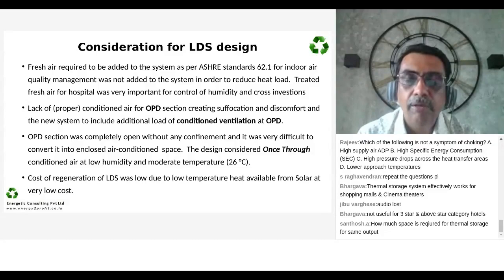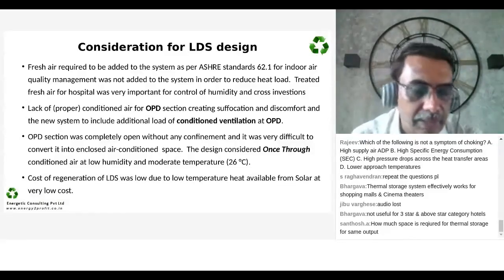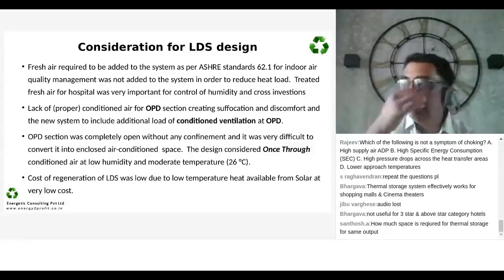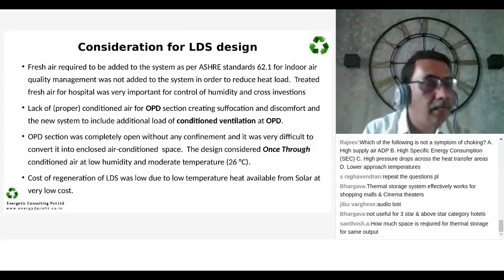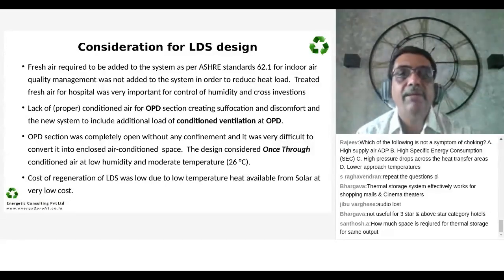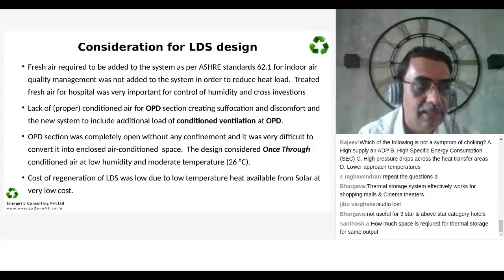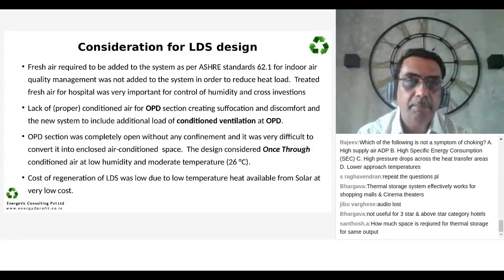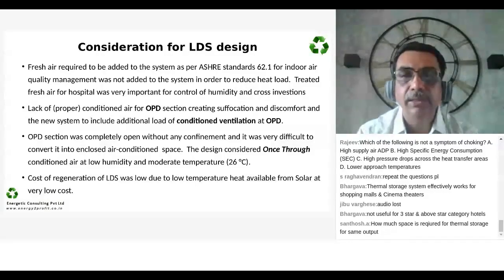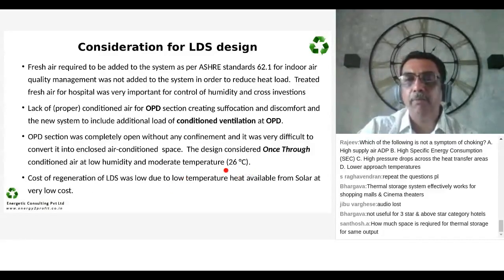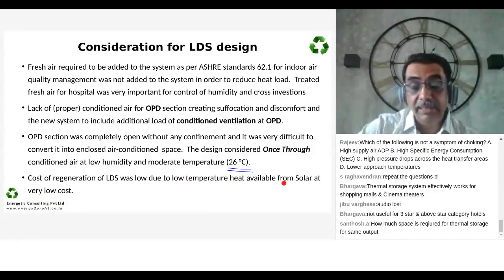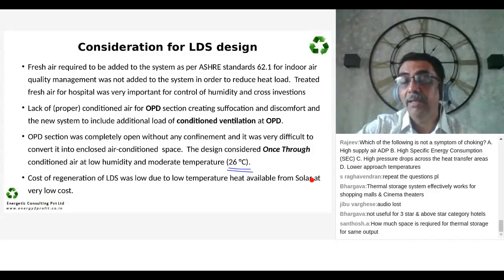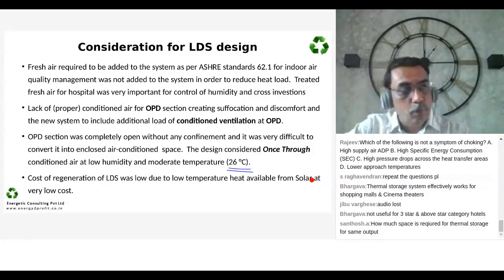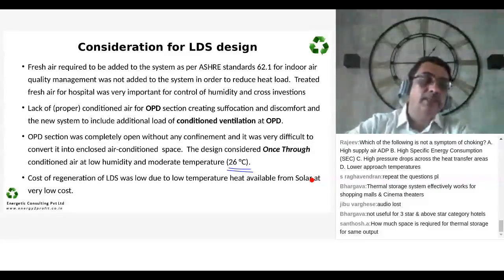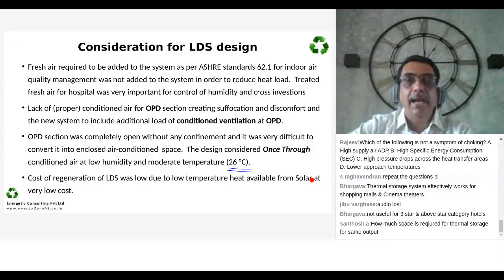It is one of the potential areas of contamination of infections. So we did it in Kalwa Hospital at that time where the area was open. So air conditioning was becoming huge. So what we did here, we had an OPD section with conditioned ventilation. We had a liquid desiccant based system which would dehumidify and cool the air with a heat pump. And that dehumidified cool air is added to the system where we could maintain a moderate temperature of 26 degrees centigrade only. This is the supply air temperature, not the conditioned space. But because the humidity was low, and in the OPD you have a large congregation of people, you have only latent heat getting added.